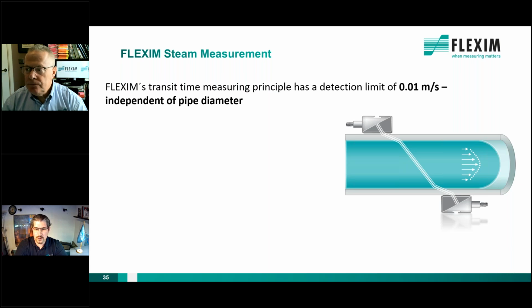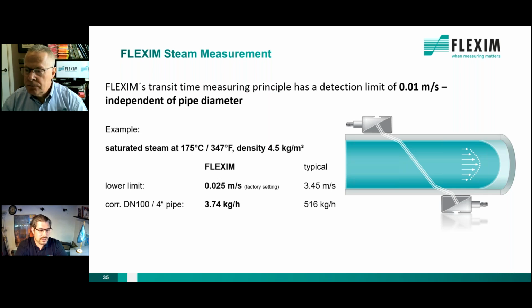We have a detection limit, so the lowest flow we can detect is 0.01 meters per second, independent of the pipe diameter. So if we take a look here at the example steam application, let's say we have steam at 175 degrees C. This would be a density of 4.5 kilograms per cubic meter, and this is the number you need to calculate those conventional flow rates. We have a lower limit here. I put it to 0.025, which is our factory setting for the low end of the flow range. Sorry, I was wrong. This would be a mass flow of 3.74 kilograms per hour. So we start measuring at 0.025 meters per second, and accordingly, the correlated mass flow in a DIN 100 pipe, 4-inch pipe, would be 3.74 kilograms per hour.